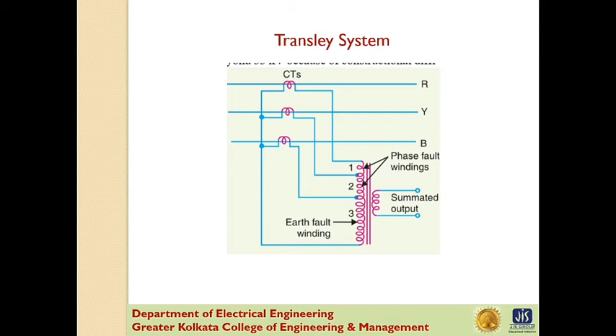Now the Translay scheme for three-phase line is shown by this picture. The relays used in the scheme are essentially overcurrent induction type relays. Each relay has two electromagnet elements. The upper electromagnet element carries the primary winding 11 and 11A. The upper element also carries the secondary winding 12 and 12A, which are connected to the lower magnet winding 13 and 13A, in series in such a way that voltages induced in them oppose each other.